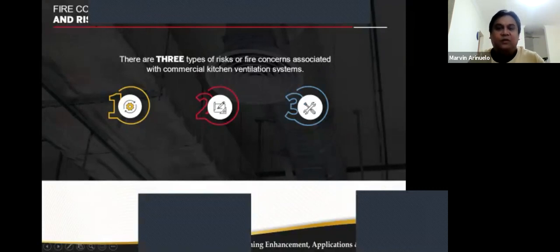The concerns with the system operation design revolve around the ventilation flow, including makeup or replacement air and exhaust flow, as well as the operating control and fire interlocking system. So what is an interlock? If you read the definition, it is a feature or mechanism used to prevent an undesired state or function from occurring. And the most serious fire interlock failures are the ones that fail to permit the suppression system to operate.